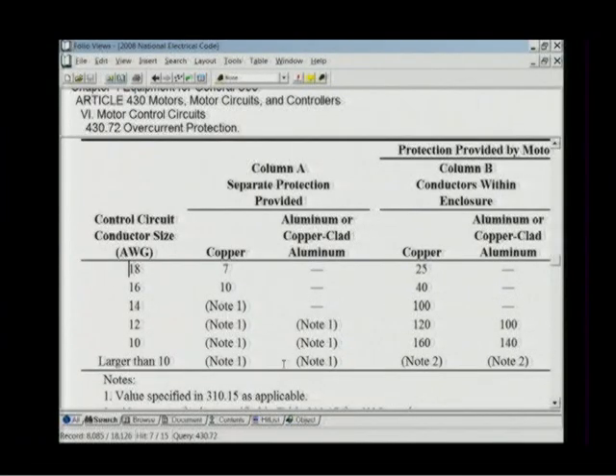What are the common size conductors that you guys use if it's not going to be 18 or 16? Now, Dan, yesterday, I think you said you use 18 and 16s quite a bit. Yeah, we use 16 on most of our control circuits. Now, do you have a separate overcurrent protection for the 16? Yes, we do, because most of our control is actually PLC, so we have separate by section of the equipment. Now is there overcurrent protection in the PLC? Well, all the outputs have overcurrent protection. They have fuses because they're triac outputs and they want to protect part of the electronic. So you use 18 gauge wire, 16 gauge wire? 16 gauge, yes. And your PLC outputs are fused. Yes. And what size fuses are you actually using? 2 amp. Okay, but you could go up to 10 amperes.